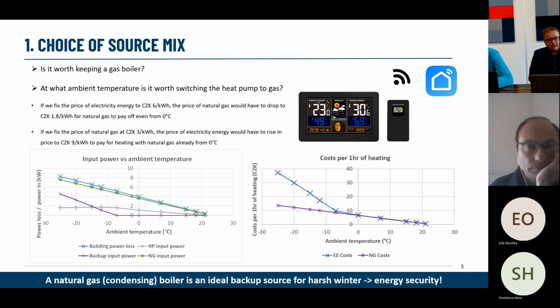Then look at what your heat pump does—that's the gray curve at the bottom. Starting from the right, at 20 degrees ambient temperature, the gray curve steadily increases down to around -8 degrees C. That's the threshold where most heat pumps no longer yield more thermal power on output relative to the electrical power you put in. You have to start complementing it with a backup, typically an electrical capsule converting electrical energy into heat. So overall consumption starts shooting up and converges with the natural gas curve—there's a threshold where it's actually effective to use heat pumps.